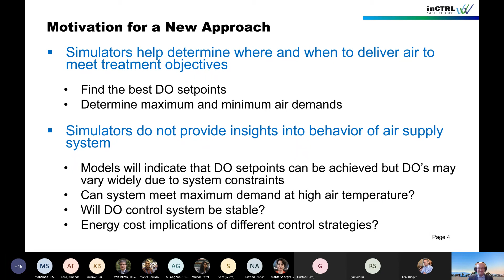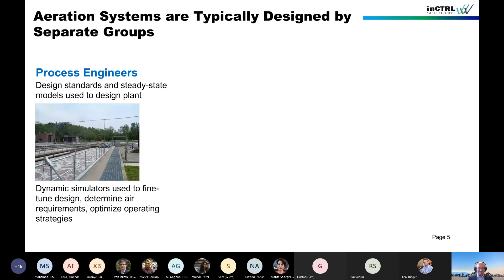Before explaining why we decided to go a different route, I want to explain that designing aeration systems is typically done by separate groups. Process engineers use design standards and steady-state models to design the plant, and may use simulators to fine-tune the design, determine air requirements, and optimize operating strategies. Then things get passed over to mechanical engineers, who use separate software to specify the blower design and the aeration piping — typically documented in separate reports.